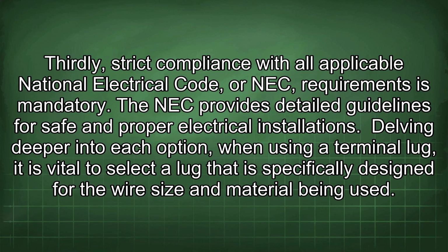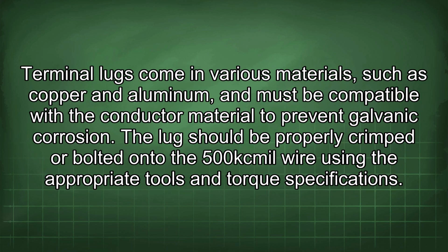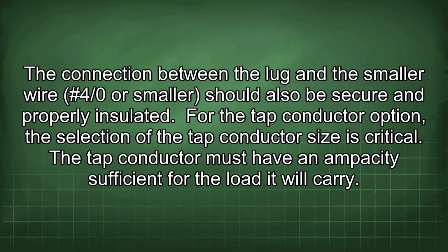Delving deeper into each option, when using a terminal lug, it is vital to select a lug that is specifically designed for the wire size and material being used. Terminal lugs come in various materials such as copper and aluminum and must be compatible with the conductor material to prevent galvanic corrosion. The lug should be properly crimped or bolted onto the 500 kcmil wire using the appropriate tools and torque specifications. The connection between the lug and the smaller wire, #4/0 or smaller, should also be secure and properly insulated.